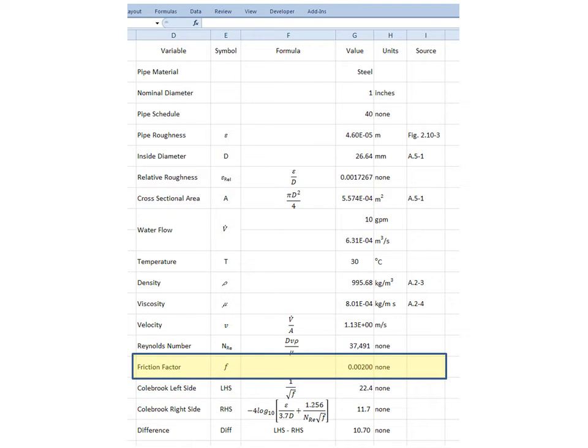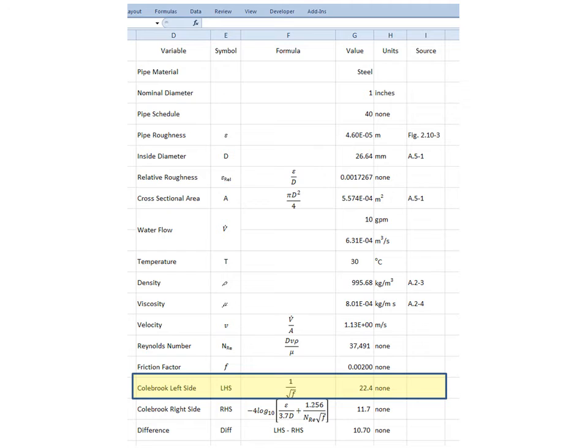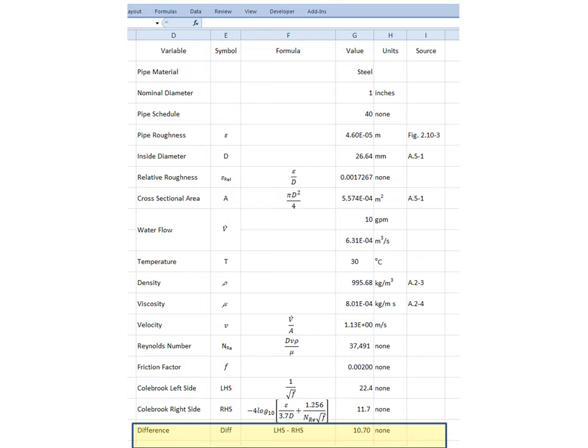Now we need to calculate our friction factor using the Colebrook equation. We don't know exactly what it will be, since it appears implicitly on both the left-hand side and right-hand side of the Colebrook equation. So the first thing we're going to do is just guess a value. In this case, I select 0.002. Calculating the left-hand side of the Colebrook equation, 1 over the square root of f gives us a value of 22.4. And the right-hand side of the equation, putting in the values, we calculate that to be 11.7. And the difference between the left-hand and right-hand side of the equation is 10.7. This indicates that the value of the friction factor has not been selected to give us a difference of 0. And I'll show you how to do this in the next slide.